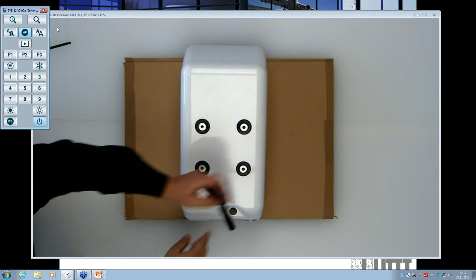If you want to know where your measurement area is, that is also not a problem. I will show you why. You can check that on site during the installation. We have a special thing here: a metal tube, which is part of the shipment of the NIRS. During the installation you can put that tube into a hole on the back. Then you can look through the tube and you will see the spot, the measurement area of the sensor. So you will be able to check during the installation where the measurement area will be. I think that's a nice way to check it, right? No problem.